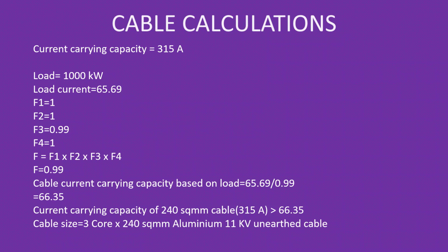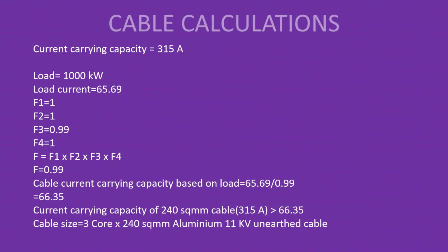In this scenario, the value is 66.35, which is very less than 315 ampere. That's the reason our cable selection is good.